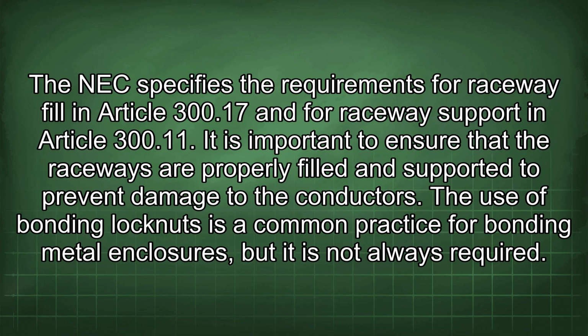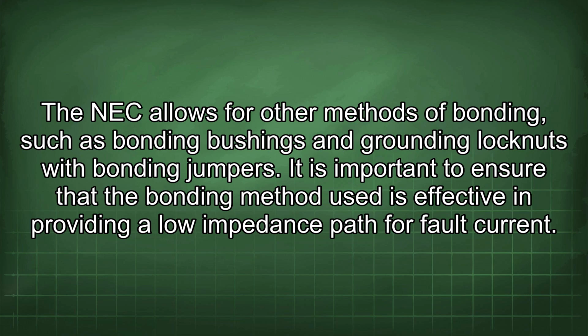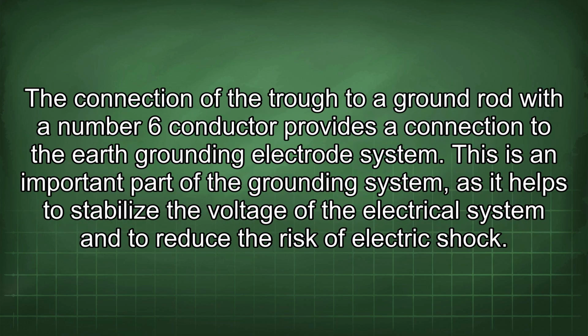The use of bonding lock nuts is a common practice for bonding metal enclosures, but it is not always required. The NEC allows for other methods of bonding, such as bonding bushings and grounding lock nuts with bonding jumpers. It is important to ensure that the bonding method used is effective in providing a low impedance path for fault current. The connection of the trough to a ground rod with a number 6 conductor provides a connection to the earth grounding electrode system. This is an important part of the grounding system, as it helps to stabilize the voltage of the electrical system and to reduce the risk of electric shock.